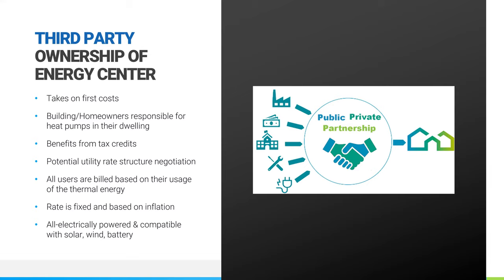And then all the users that are connected to that are billed based on their usage of that thermal loop, which is very simple. There's energy meters that are already commercially available. And the setup in front of your home would look nothing different than your gas or water hookups that you would already see. So if somebody was not paying their bill, the owner of that thermal utility could come in very easily and basically shut off the water pipes to that building and you would no longer have heating and cooling. And then again, everything is all electrically powered and compatible with solar, wind, and battery there on that site. So you can really quickly see how having a third party entity come in and own the energy asset, and then having entities hooked to that asset, all powered by electric, wind, and solar, you've got the potential for a microgrid in that area very quickly realized.